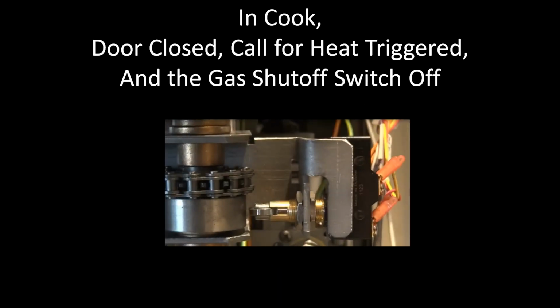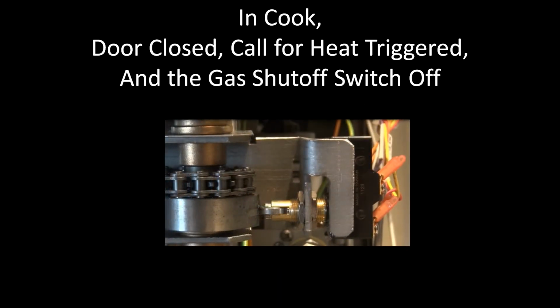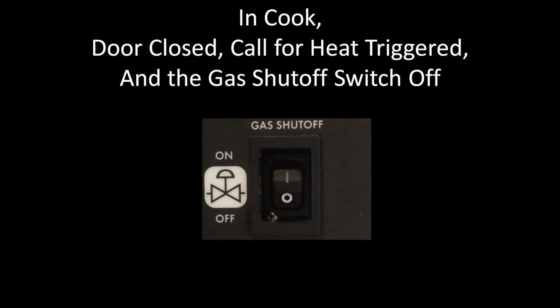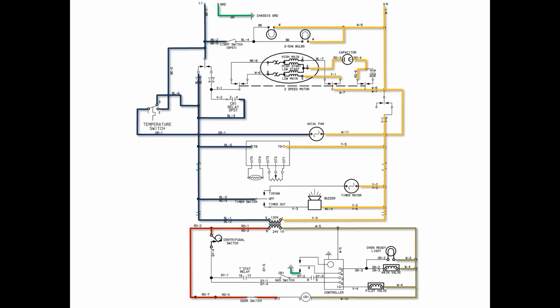Next, we will close the door while the oven is calling for heat, but the gas shutoff switch will be off. When the door is closed, CR1 receives coil voltage, allowing it to pass voltage to the motor. When the motor is running, the centrifugal switch closes and voltage is sent to and out of the heat relay because a call for heat is present. The voltage is stopped at the open gas shutoff switch.